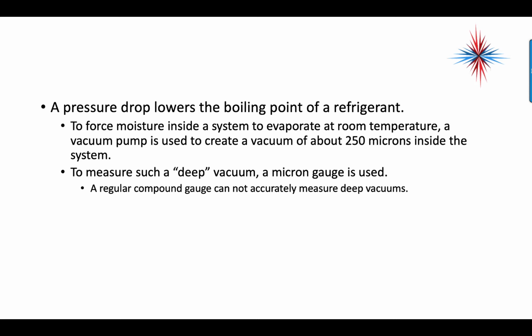The pressure drop lowers the boiling point of a refrigerant. To force moisture inside a system to evaporate at room temperature, a vacuum pump is used to create a vacuum of about 250 microns in the system. To measure such a deep vacuum, a micron gauge is used. A regular compound gauge cannot accurately measure deep vacuums, so you have to have a gauge that goes into microns.